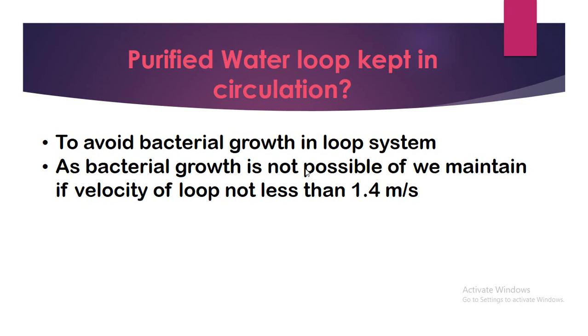First of all, the basic reason is to avoid bacterial load in the loop. We keep the purified water loop in circulation. If the velocity of the loop is not less than 1.4 meters per second, then bacterial growth is not possible. This is why we maintain the purified water loop at 1.4 meters per second or keep it in circulation.